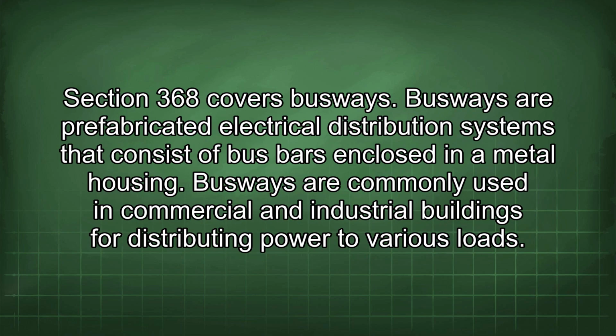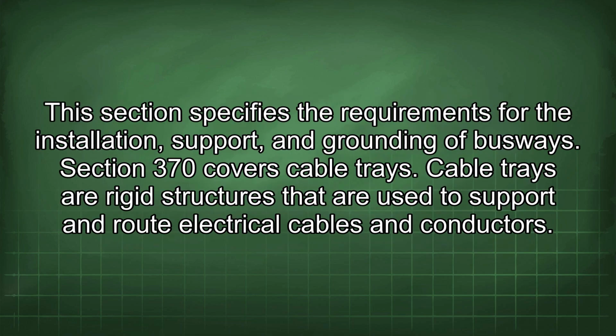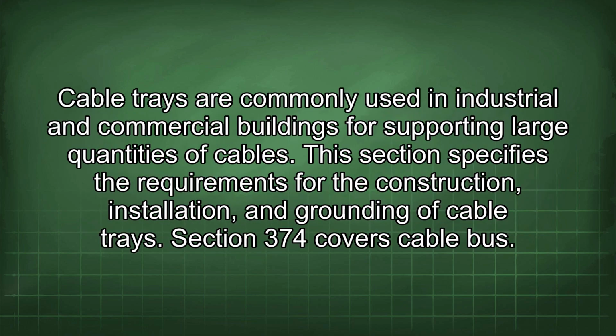Section 368 covers busways. Busways are prefabricated electrical distribution systems that consist of busbars enclosed in a metal housing. Busways are commonly used in commercial and industrial buildings for distributing power to various loads. This section specifies the requirements for the installation, support, and grounding of busways. Section 370 covers cable trays. Cable trays are rigid structures that are used to support and route electrical cables and conductors. Cable trays are commonly used in industrial and commercial buildings for supporting large quantities of cables. This section specifies the requirements for the construction, installation, and grounding of cable trays.